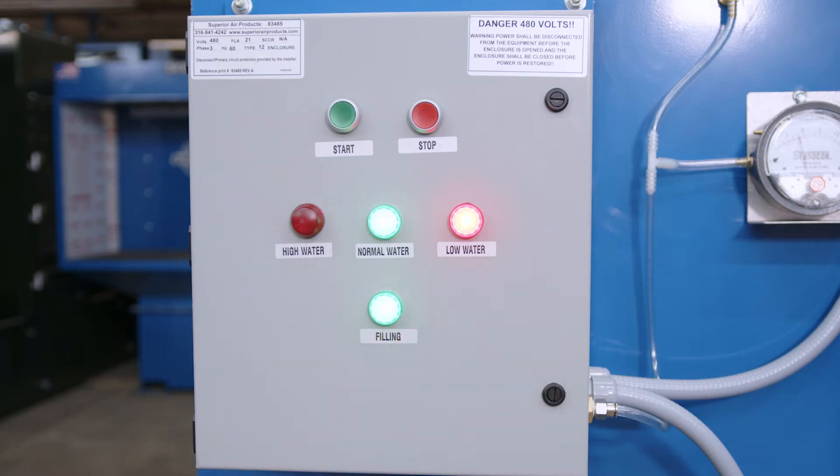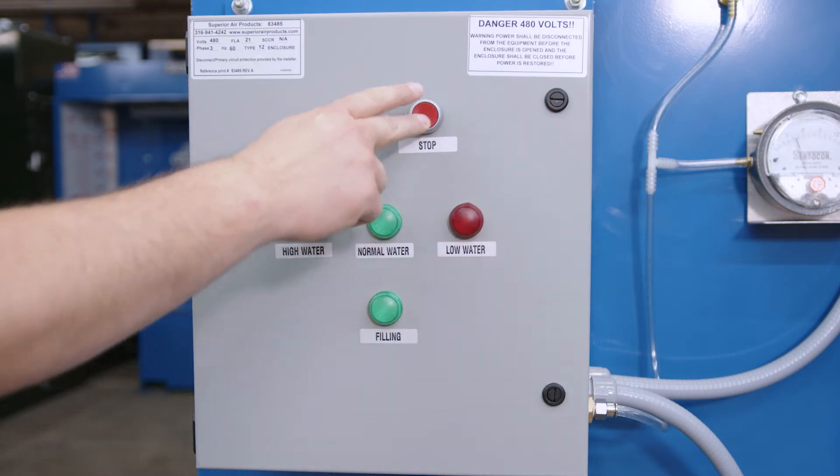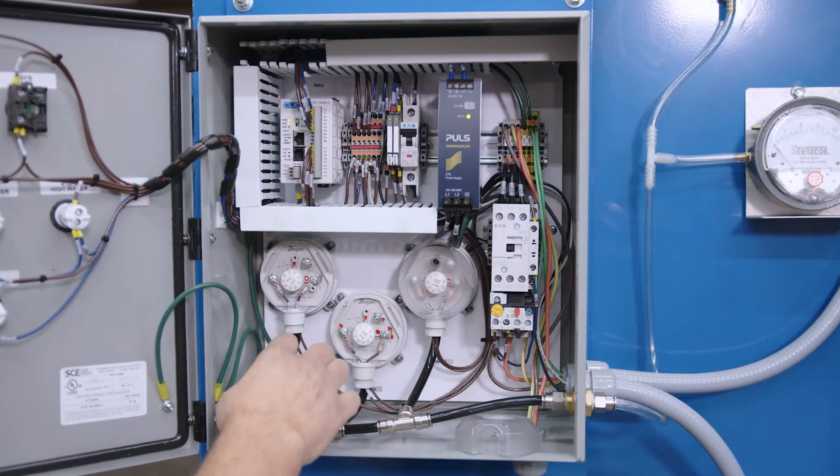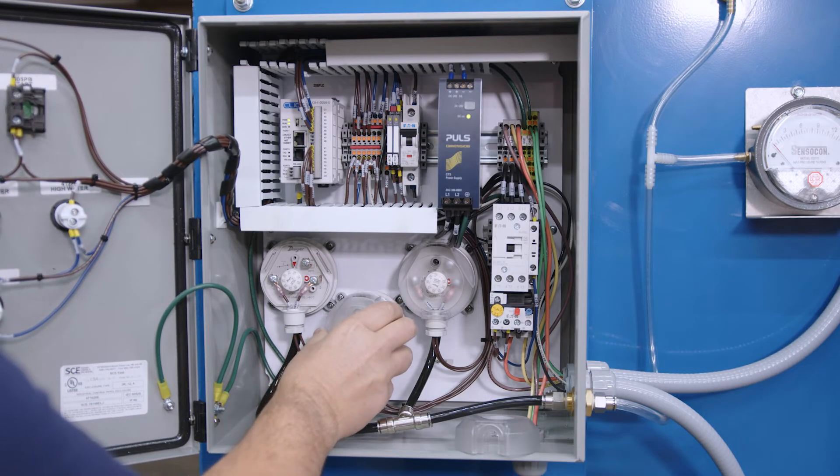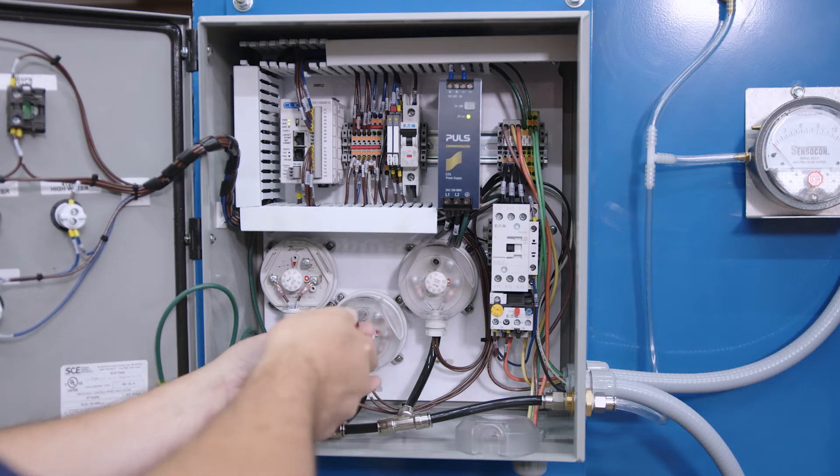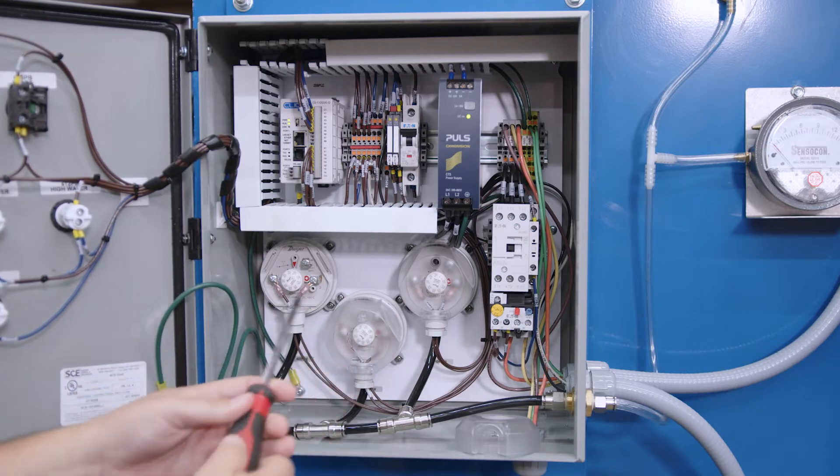This would signify a situation where water levels are not satisfactory to ensure proper operation. The middle or nominal pressure switch is the level that dictates the water level the unit will normally operate at. Each of these switches is preset during factory testing but can also be set in the field at another desired level of operating parameters.